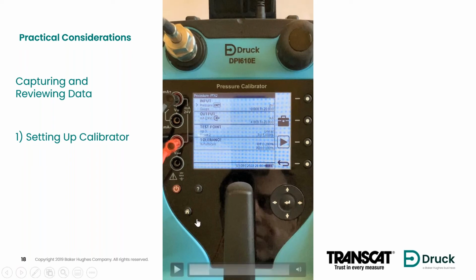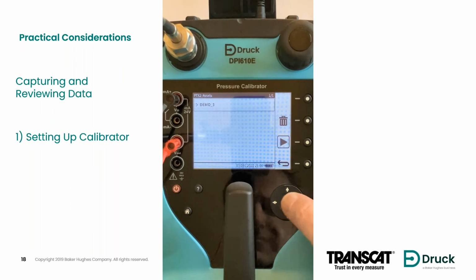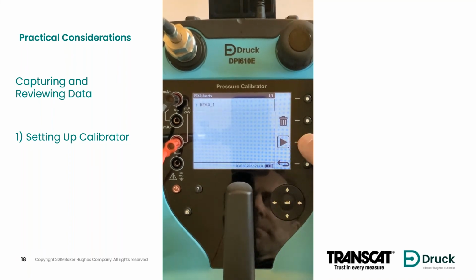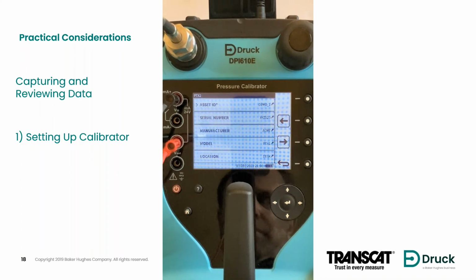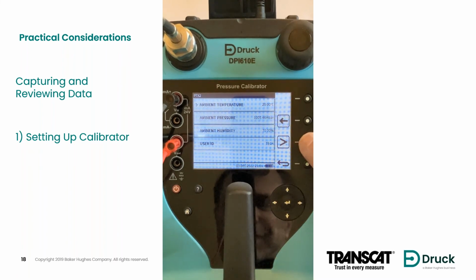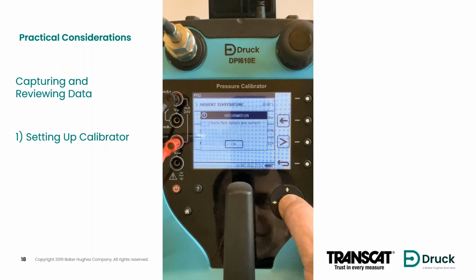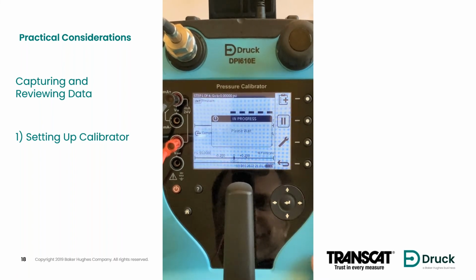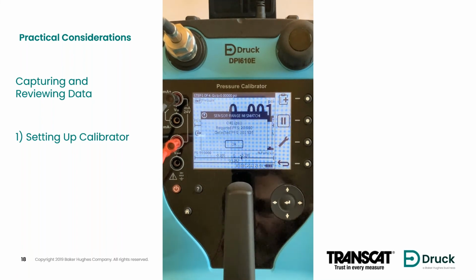What I'll do now, and the next step, is go into my catalog of assets, which you again can save on the calibrator itself and then call up the actual device or device type that you're going to be checking. So I've set up all my parameters on the procedure. Then I go in and I only have one on this particular unit, so I'm going to pick that one. It shows me the asset ID, serial number, manufacturer, model, and location.